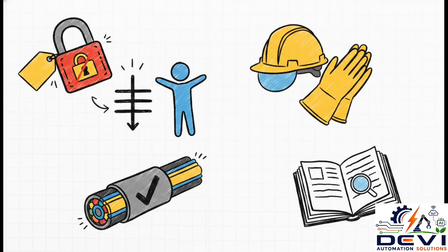And because we are dealing with serious high voltages and heavy machinery here, the guidelines stress that safety is completely non-negotiable. They mandate implementing lockout-tagout, or LOTO, before you even think about opening a panel. Proper earthing isn't just about reducing noise, it literally saves lives. The sources also emphasize making sure technicians are wearing proper electrical PPE, double-checking cable sizing to prevent electrical fires, and always sticking strictly to the manufacturer guidelines. Cutting corners on the shop floor simply isn't an option.